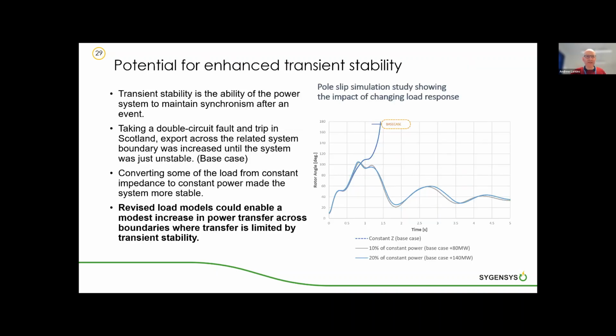The second area we looked at was transient stability. And this is the ability of a power system to maintain synchronism after an event so that all the generators stay in step with each other. Again, ESO very helpfully gave us a double circuit fault case with a trip event in Scotland. And we increased export across this boundary until the system was just unstable. And this is the base case shown on the graph on the right here. And then we converted some of the load from constant impedance to constant power. And what we found unexpectedly was this helped the system become more stable. To be honest, we were expecting the opposite, but it actually improved system stability slightly. As you can see from these two other curves on the right here, with 10% and 20% of constant power in the study. So this suggests that actually revising load models could give some modest increase in power transfer across boundaries that are limited by stability issues.